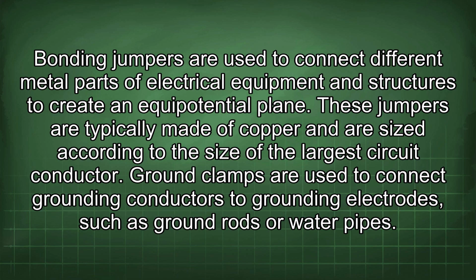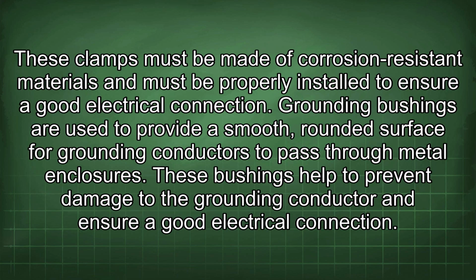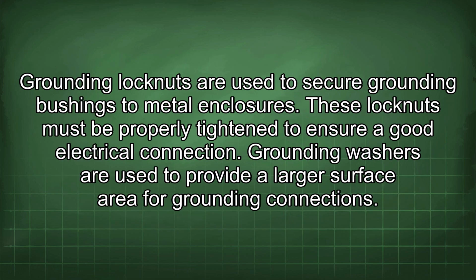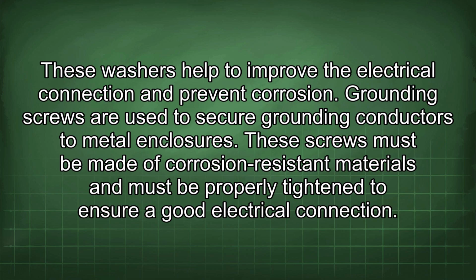Ground clamps are used to connect grounding conductors to grounding electrodes, such as ground rods or water pipes. These clamps must be made of corrosion-resistant materials and must be properly installed to ensure a good electrical connection. Grounding bushings are used to provide a smooth, rounded surface for grounding conductors to pass through metal enclosures. These bushings help to prevent damage to the grounding conductor and ensure good electrical connection. Grounding lock nuts are used to secure grounding bushings to metal enclosures. These lock nuts must be properly tightened to ensure a good electrical connection. Grounding washers are used to provide a larger surface area for grounding connections. These washers help to improve the electrical connection and prevent corrosion.